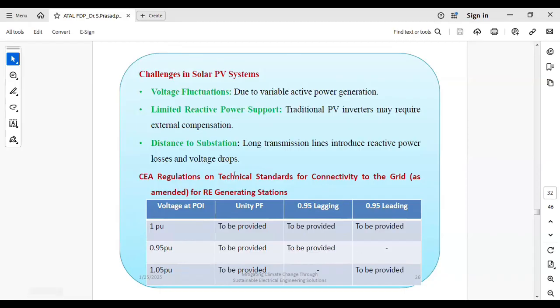So this is the CEA regulation, and you have to perform this task and produce the report. All these cases you have to run, produce the report and submit it to the utility grid, and they need to verify whether you have accurately determined the capacity of the reactive power compensating device or not. Your PV plant, when connected to the grid, should not disturb it. It should not absorb reactive power unless instructed by the grid utilities. You should always supply reactive power support at the point of interconnection, and we verify that by conducting this test.